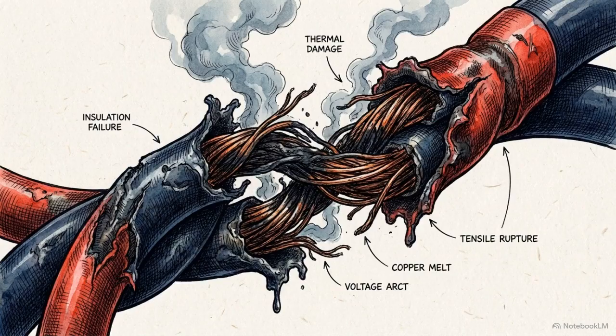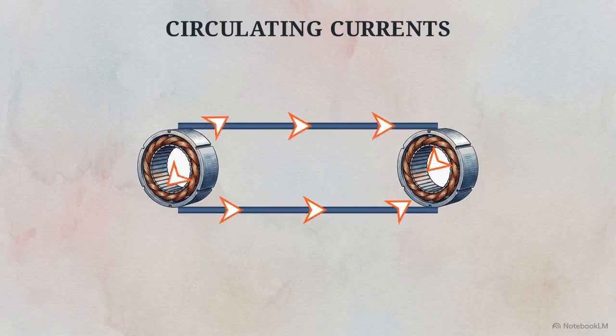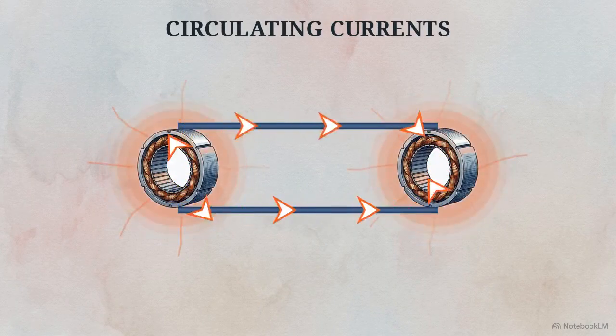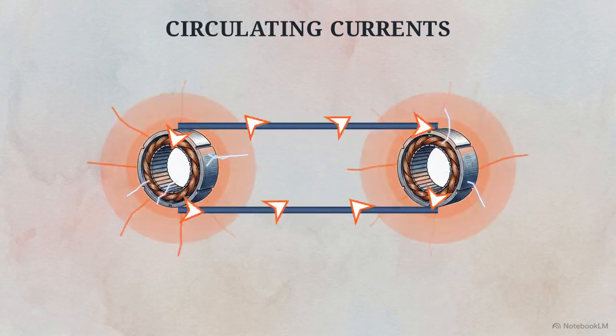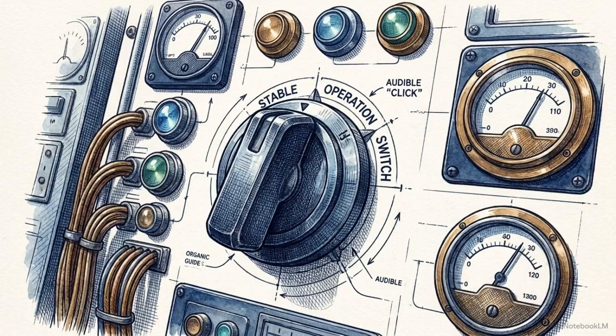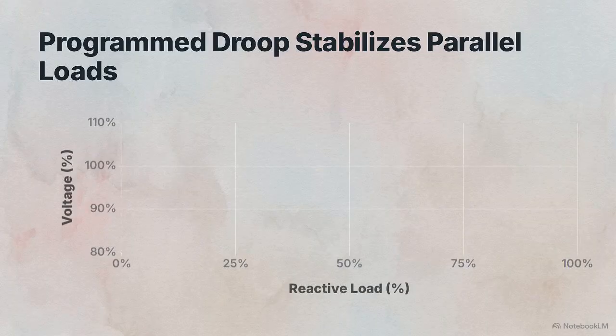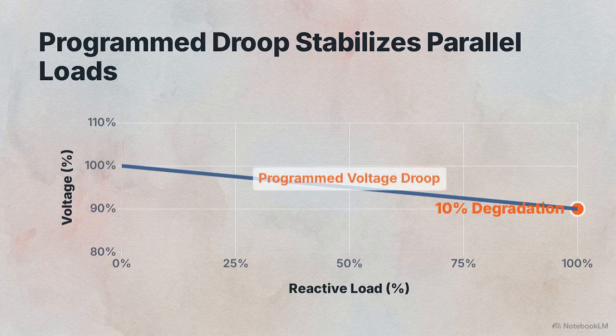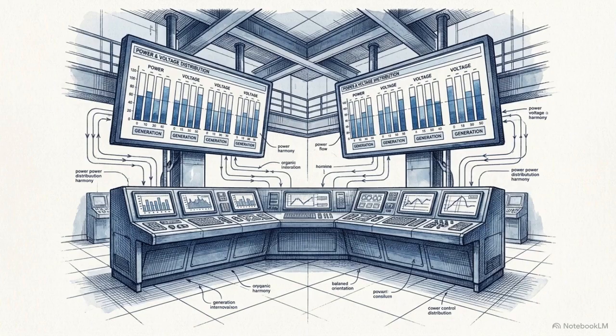If two parallel units try to rigidly hold perfect voltage without compromise, the system breaks down electrically. Highly destructive circulating currents will flow continuously between their stators, generating massive heat and potential insulation failure. The electrical solution to this is voltage droop. The AVR utilizes a 4 to 10% programmed degradation to passively and safely share lagging reactive current across the parallel units. Intentional degradation is a universal law of parallel generation. It applies equally to mechanical speed via the governor and electrical voltage via the AVR.